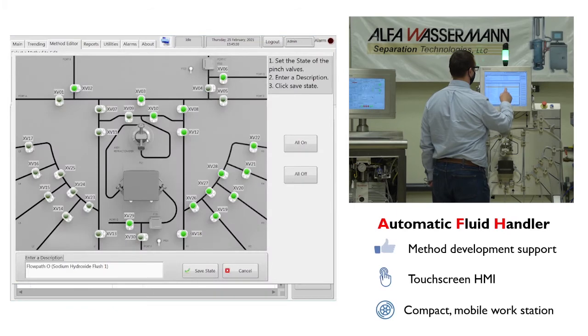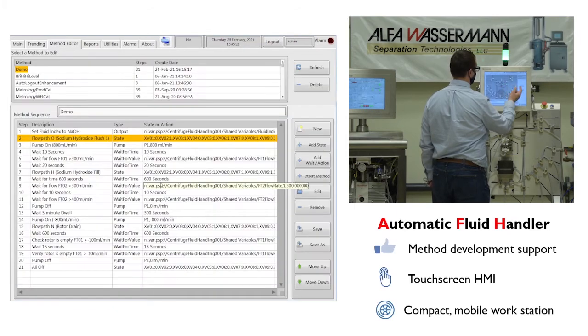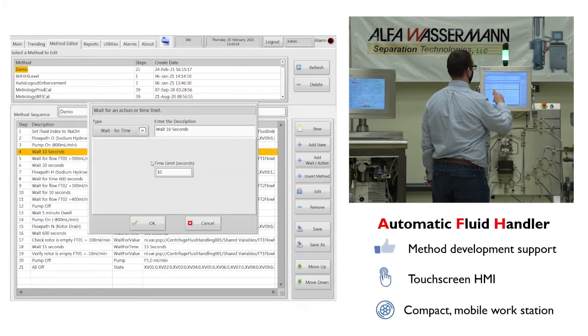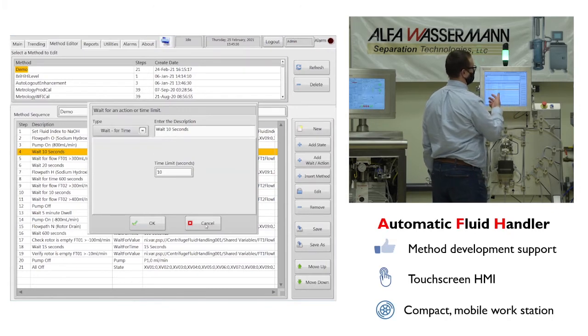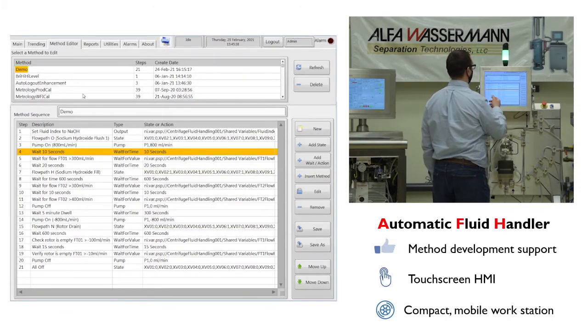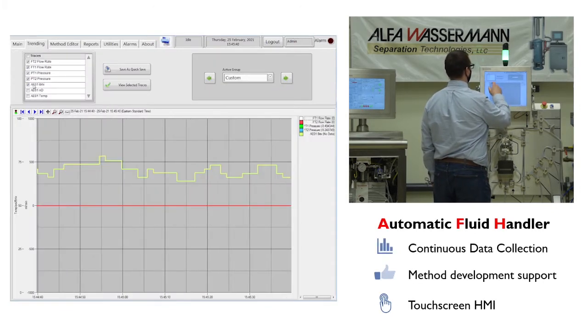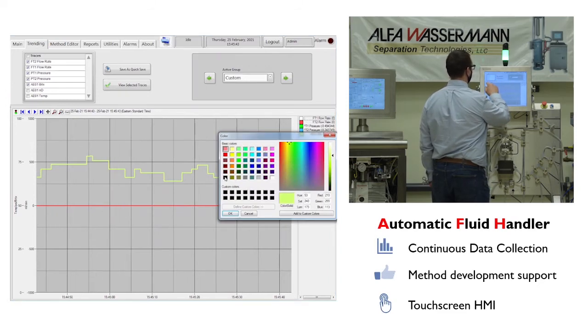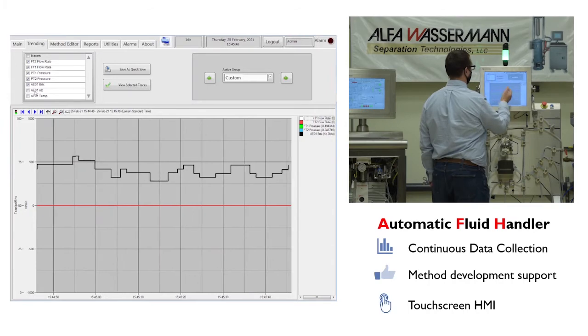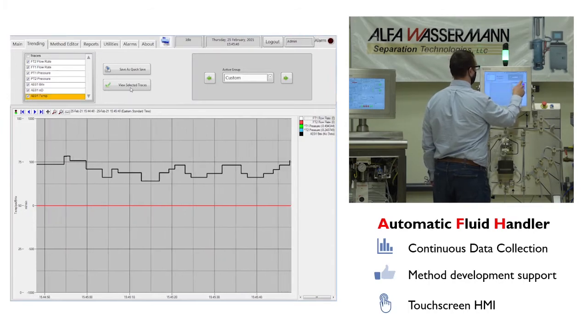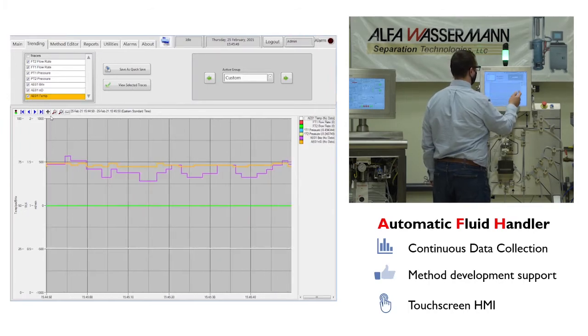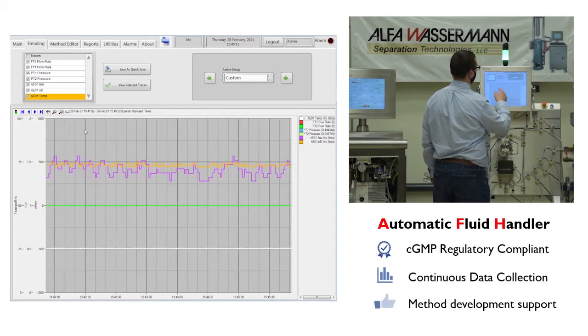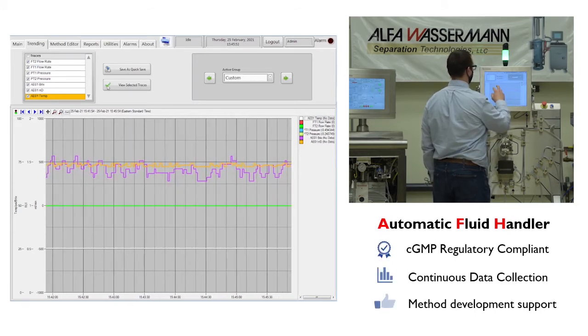This intuitive interface allows custom protocols to be rapidly developed and implemented into any sanitation, rinsing, filling, or fractionation steps. Over here in the trending tab, an operator can see a continuous real-time display of real-time and stored reporting of all the system's instruments. This dynamic screen aids in system monitoring and really eases regulatory compliance.